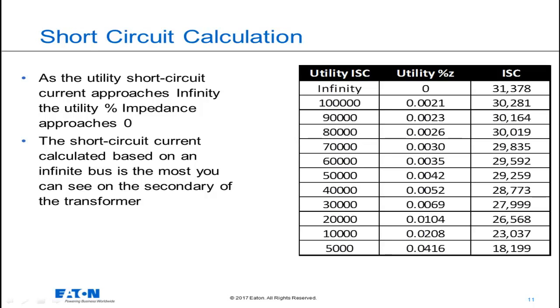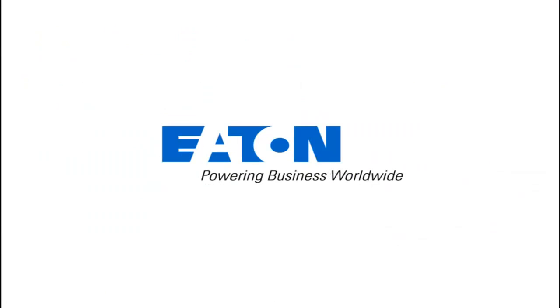Recognize that as the utility short circuit current approaches infinity, the utility percent impedance is approaching 0, and the short circuit current calculated on the secondary of the transformer is getting larger because we're removing the utility impedance from the circuit and from our equations. As I approach infinity from the available fault current from the utility, I am getting to the most fault current I could possibly get on the secondary of the transformer, hence the infinite bus. Thanks for sharing your time to talk about this technical topic.